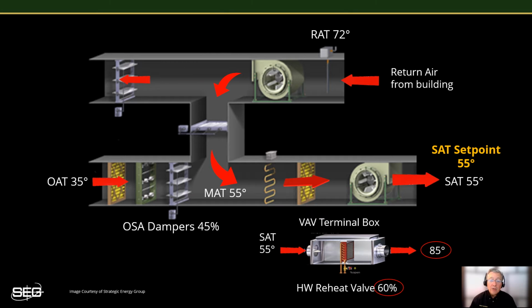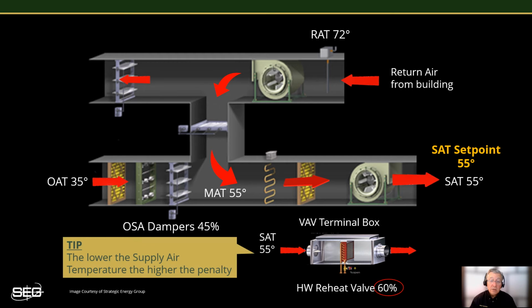Under cold outside air conditions like this, reheat will be needed at many of the terminal boxes. So now the question is, should the air handler supply air temperature set point remain at 55 degrees under these conditions? In general, no. During cold weather, the lower the supply air temperature, the higher the reheat penalty is.